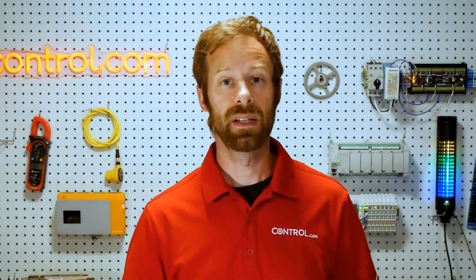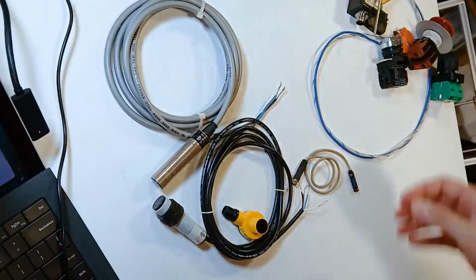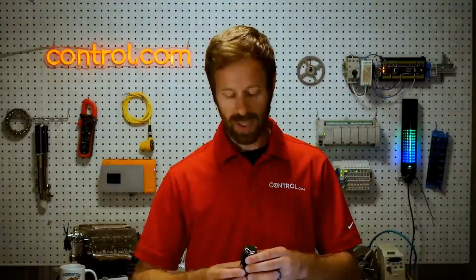Also, that adjustability and flexibility, like I said with the mechanical sensors, sometimes it's nice to not have to change anything, but it usually is better for a well-optimized system to have sensors that we can adjust when needed. Also, that status indicator can be a great troubleshooting tool. With very few exceptions, some exceptions being some relays have lights when a coil is energized. Those ones tell when it should be activated and not.